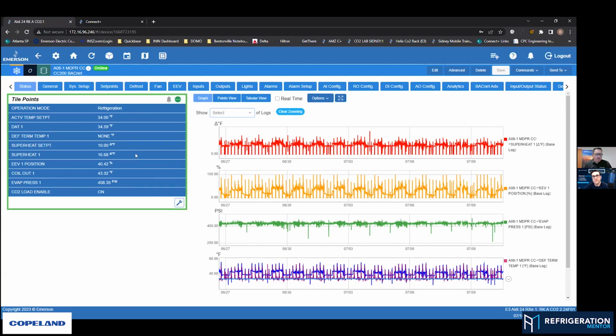Then, with correct sensor placement already done and a well-insulated suction line probe coming out of the evaporator, the way I do it is operate one case at a time. When starting them up, you try to make that time, though it's hard sometimes with end users and their schedules, and someone needing to load the case behind you with a cart full of stuff. But you try to do one case at a time. If I find an issue in a case, I'm not necessarily resolving it right there -- it's easy to shut that case down, make a note that we have an issue with XYZ, keep a working action list of what to get back to, but don't let that stop the startup.